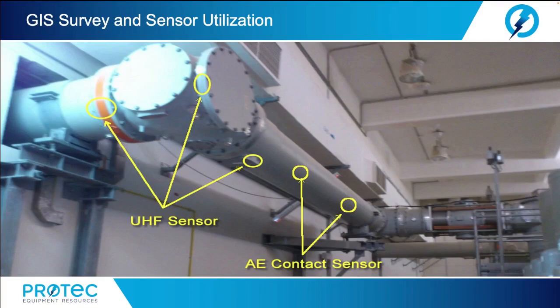Here we see sensor utilization in GIS surveys. Again, the UHF sensors can be used anywhere where we have gaskets or fittings, where the ultra high frequency signals can escape the metal cladding. Also, we can use in-tank testing methods, utilization of the AE contact sensors.